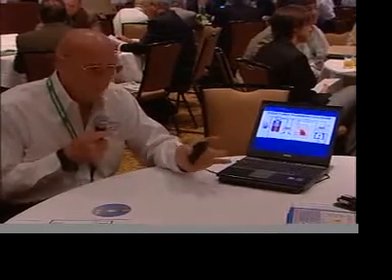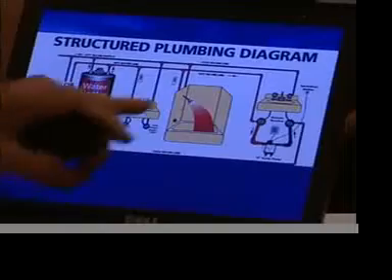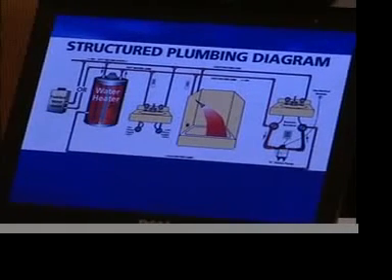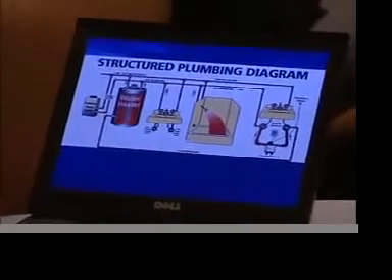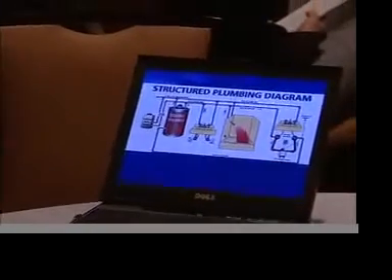That's a bad idea. You don't want to recirculate water constantly — you want to get it there when you need it but not circulate it when you don't. In standard structured plumbing, which is typical of 97 to 98% of all homes, you've got your water heater at one end of the house and your fixtures at the other. Those fixtures at the far end are where you waste a lot of hot water. Studies have indicated an average of 7,000 to 12,000 gallons a year lost down the drain just waiting for hot water — you may actually be losing more water waiting for hot water than in actual use.